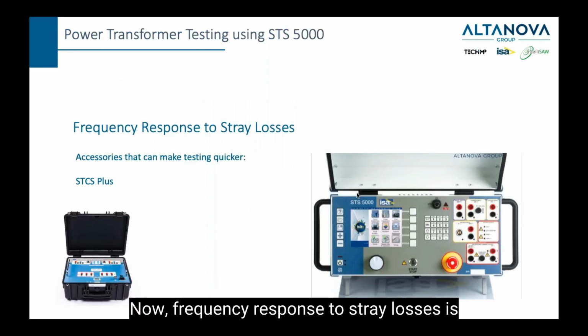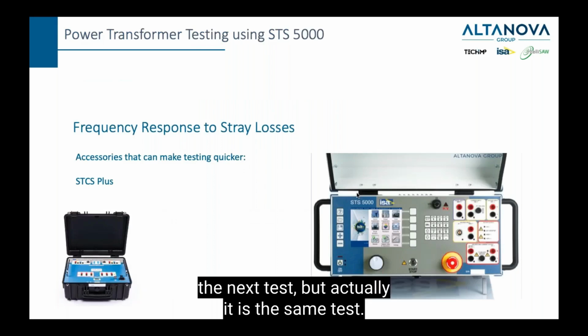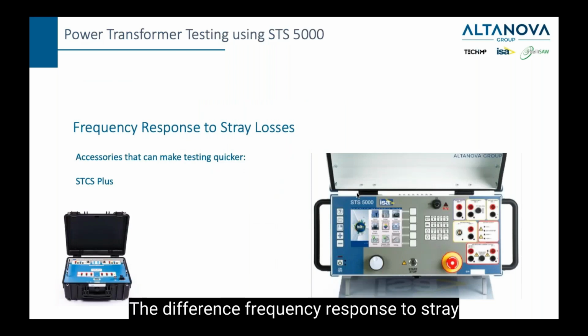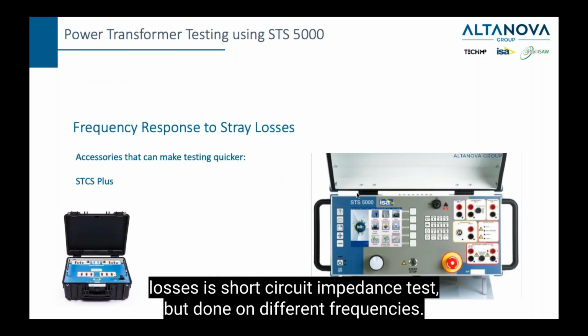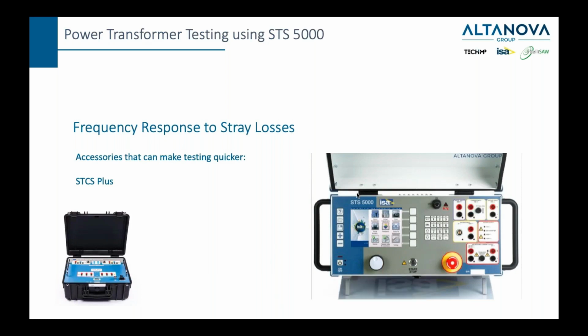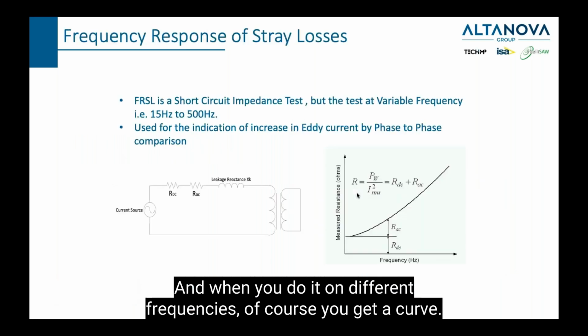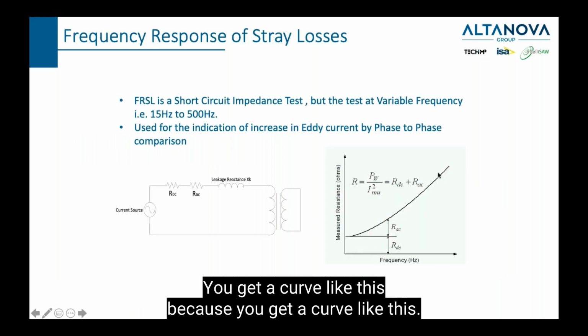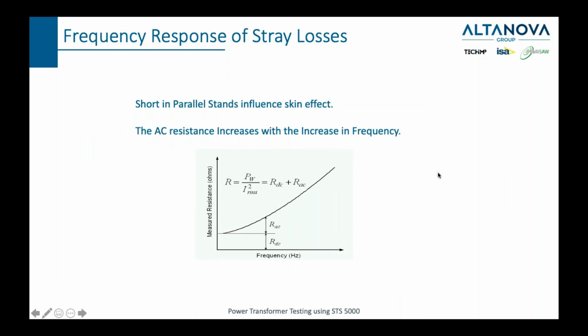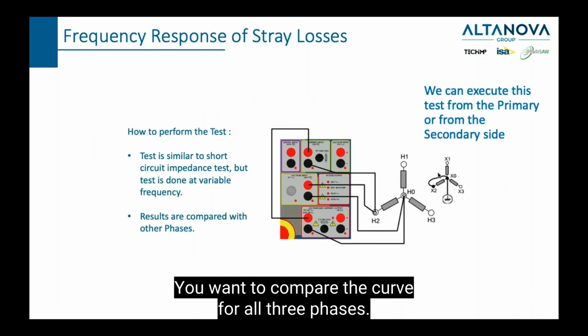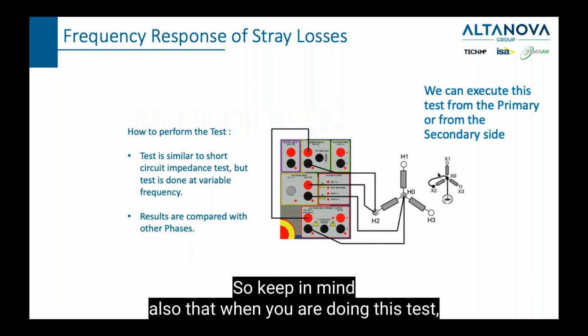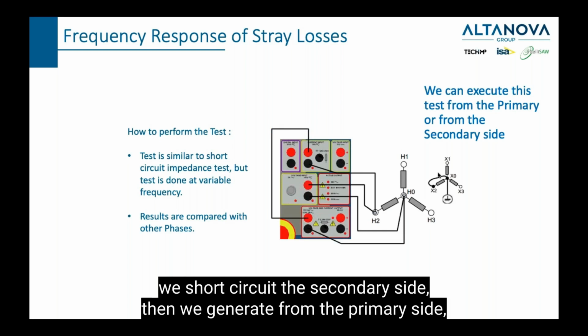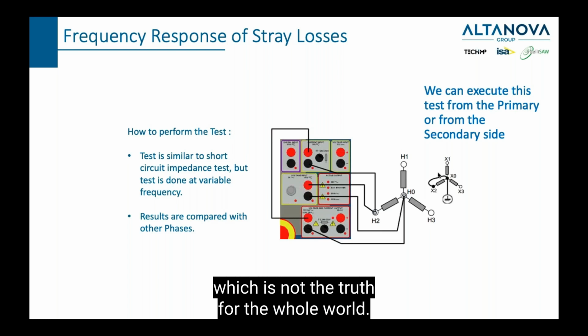Now, frequency response to stray losses is the next test, but actually it is the same test. The difference is that frequency response to stray losses is the short circuit impedance test, but done at different frequencies. And when you do it at different frequencies, of course, you get a curve. You get a curve like this, and because you get a curve like this, you want to compare the curves for all three phases. So keep in mind also that when you're doing this test, we short circuit the secondary side and we generate on the primary side, which is not the truth for the whole world.